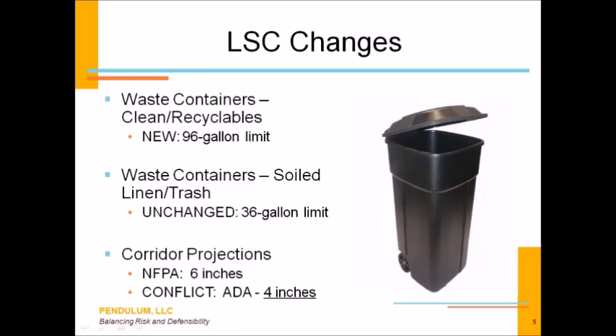So outside of a protected area like a soiled utility room or a protected storage room that is a one-hour rated construction with a self-closing rated door and fire sprinkler system, you are only allowed to have 36-gallon limits outside of those protected areas. Speaking of corridors, when it comes to projections within the minimal 8-foot wide corridor that's required in a healthcare facility, NFPA says that you can now have a 6-inch projection or protrusion within that 8-foot corridor.